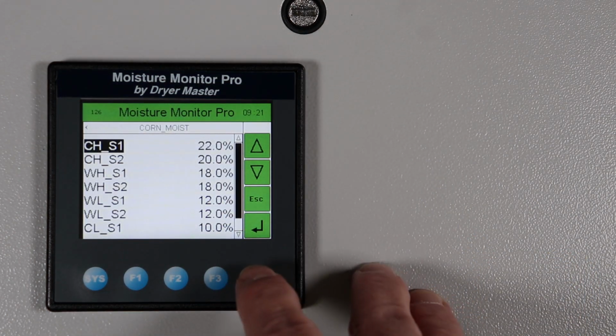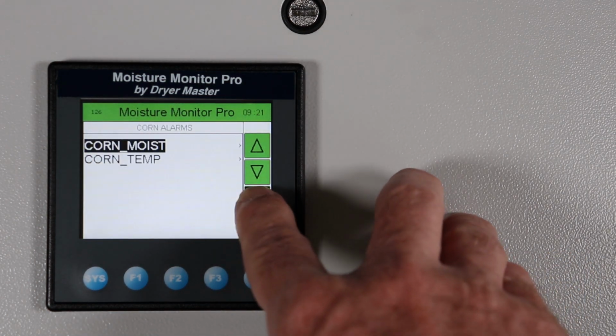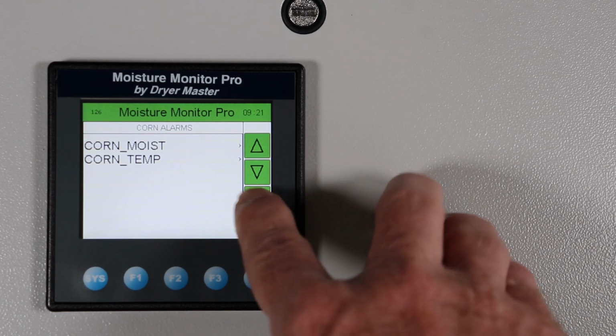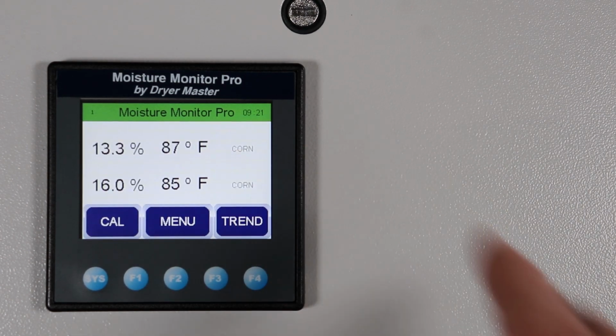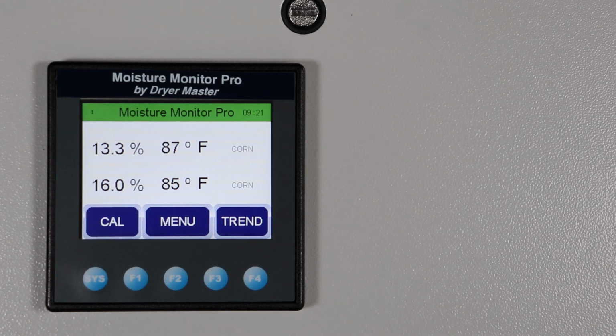Okay, and if we go back to the main screen, we're going to see what happens if you go into an alarm. So we just keep hitting the escape key, and we get back there. Now we're going to get the moisture. This is going to be a critical alarm because we're over 22. And there's a delay before the alarm goes on. Essentially, so you don't have nuisance alarms, so something weird happens just for a second or two. So there's an alarm delay. I'm going to show you in a second how to set that up. The default is 10 seconds.